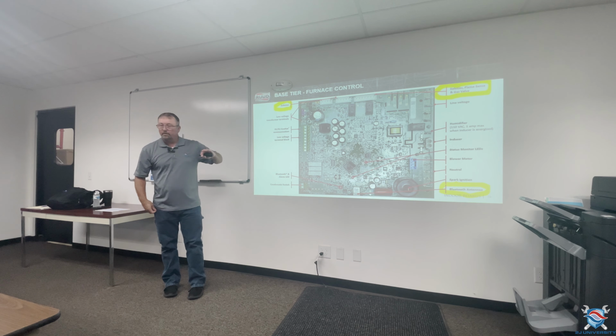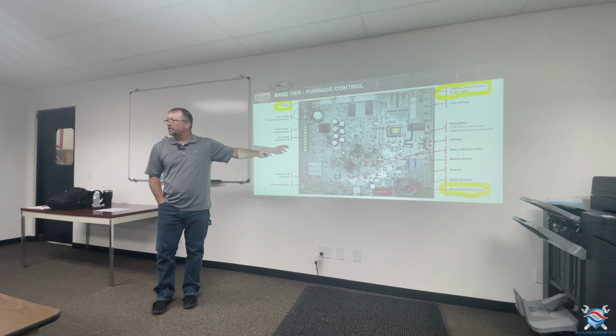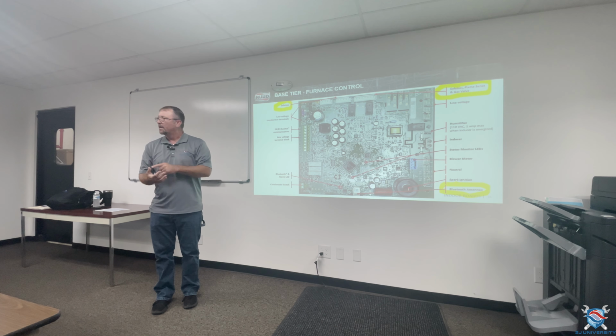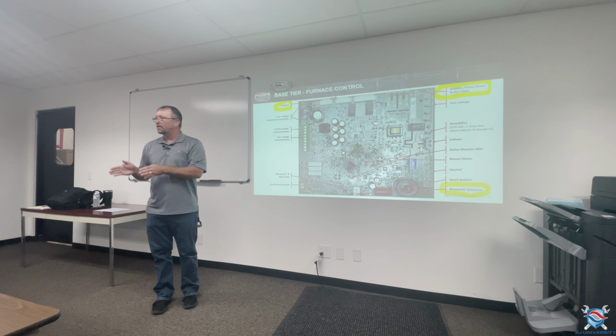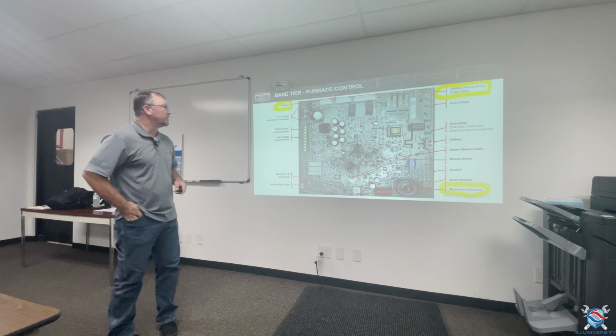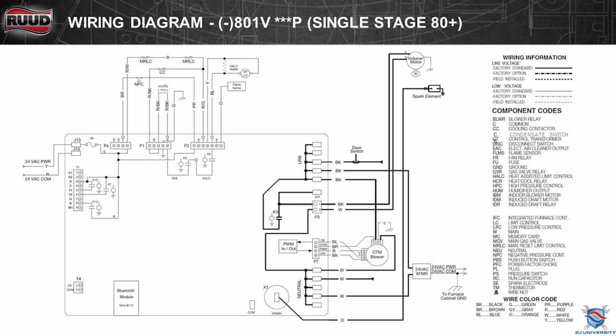Gives you a little bit better code efficiency. So when you're looking up codes, it gives you a little bit better direction on what you're looking for at that point. A little bit on the wiring diagram, I just wanted to show you that. So your flame sense comes in here, your gas valve goes out, comes right back to the board. You don't see any safeties built in that circuit. So everything's a home run.